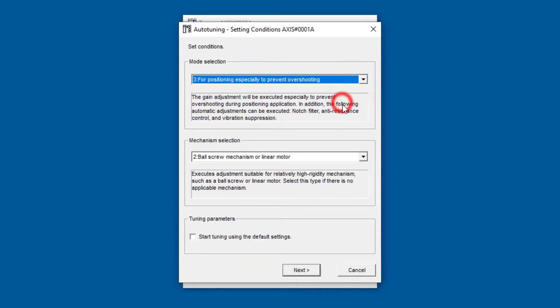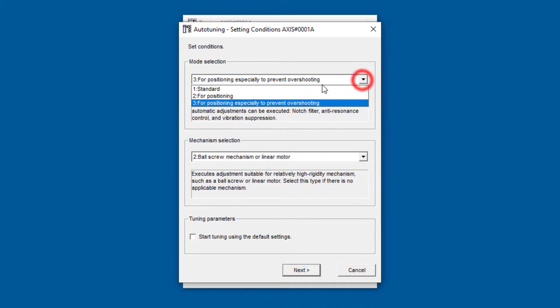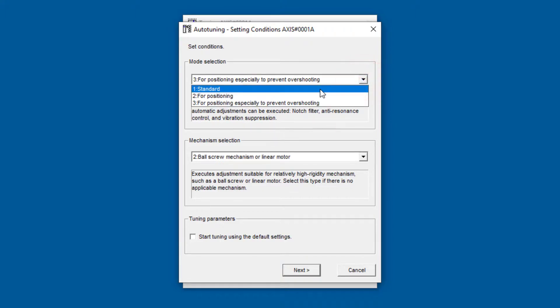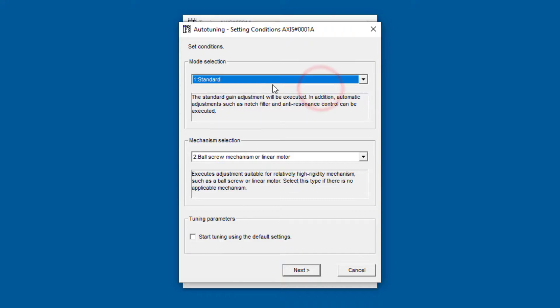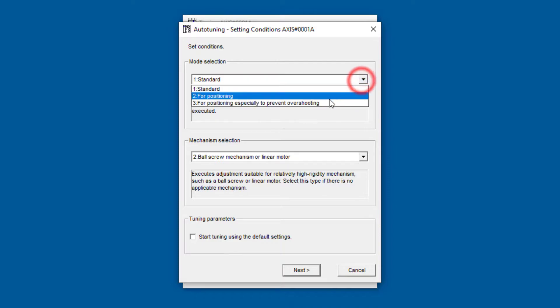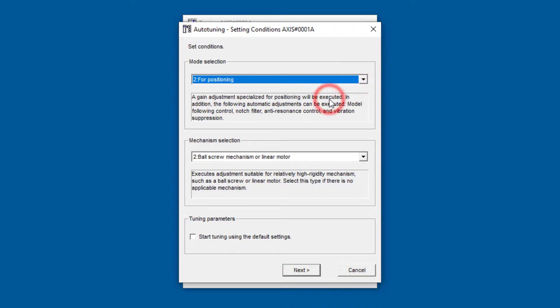Mode selection 3 also uses model following control, even though it's not mentioned here. If you need vibration suppression, you don't want to choose number 1 standard because you don't have model following control or vibration suppression. So those two go hand in hand. Let's leave it at the default here of number 2.